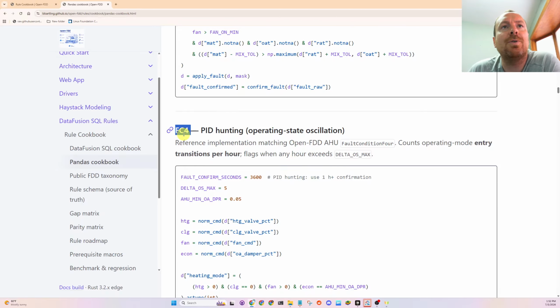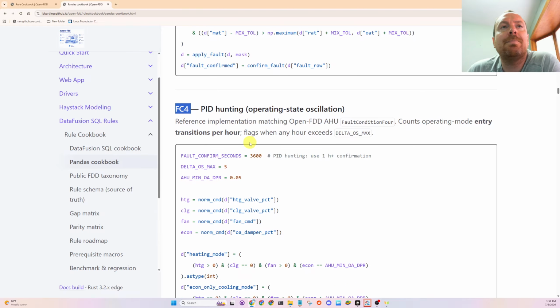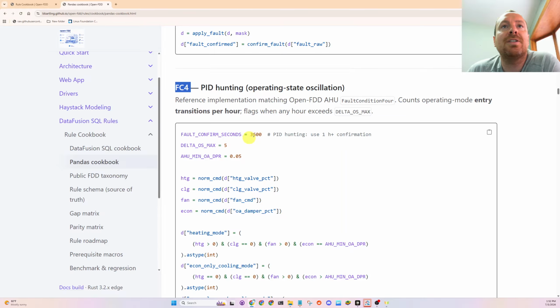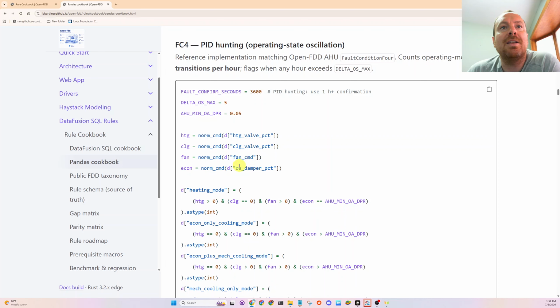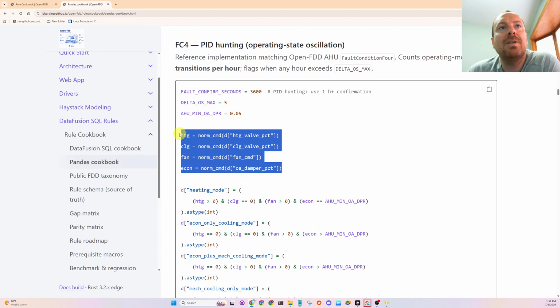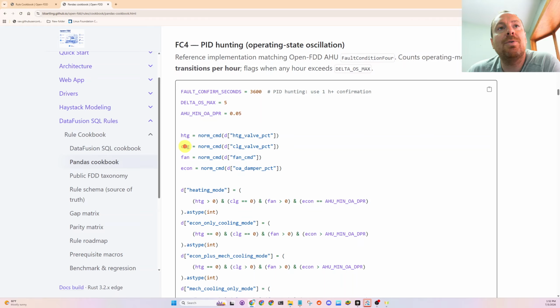This is fault condition 4 defined by ASHRAE Guideline 36. What it does is look at an hour's worth of data, then calculates whether the air handling unit is in heating mode, cooling mode, fan-only mode, or economizer cooling mode, by looking at the outside air damper percentage, fan command, cooling valve, and heating valve positions in the data to determine which mode the air handling unit is in.